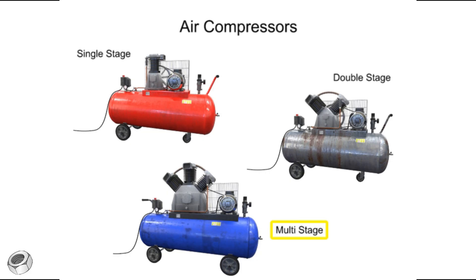If pressures of more than about 175 psi are needed, multi-stage compressors should be used. On these larger compressors, cooling may take place by circulating water instead of air. To reach a pressure of 2500 psi, as many as 6 or 7 stages may be needed, with cooling between each stage. Their versatility makes compressors one of the primary components in air production.